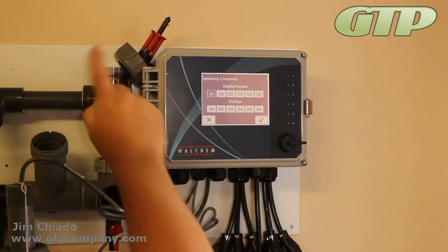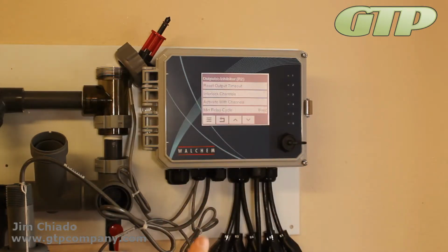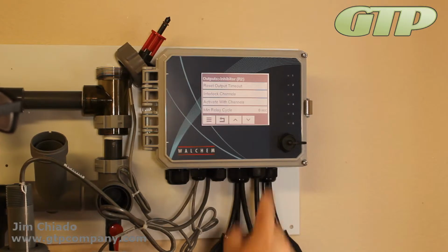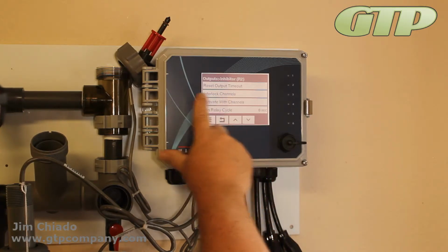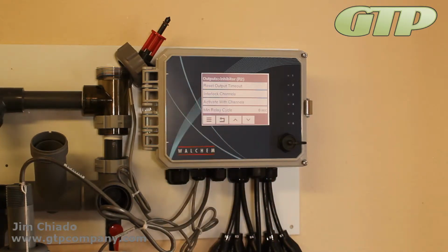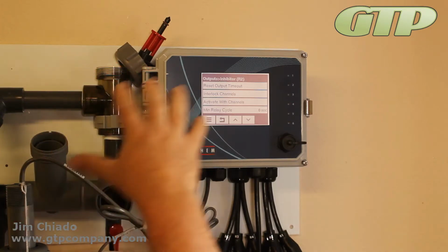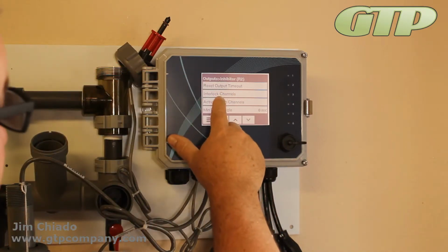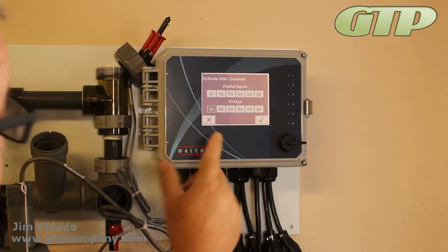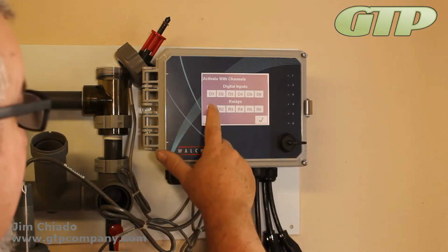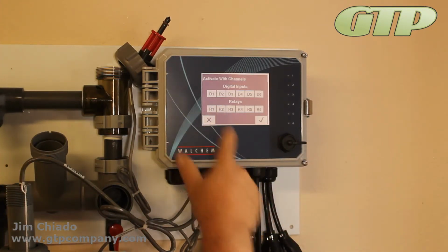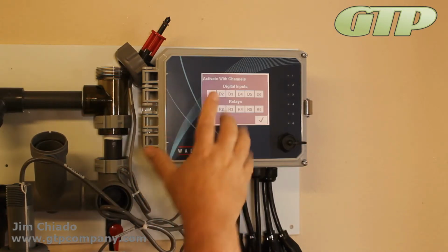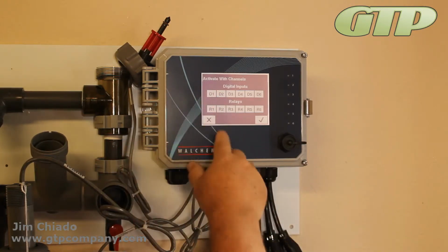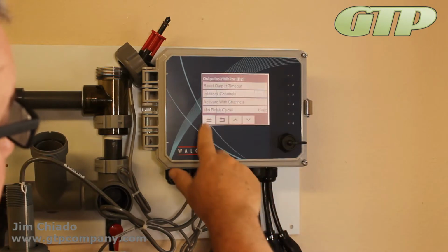Interlock channels, I want you to pay attention to. Make sure that your flow switch is done. Just because you set the flow switch doesn't mean it's going to work. Activate with channels, which is the opposite of interlock. Activate with: if something else comes on, I want this to come on at the same time. You could be redundant and tell it R1, that's fine. But you don't want it to come on with the bleed, because this is feed after bleed. Okay, don't forget that. And check.